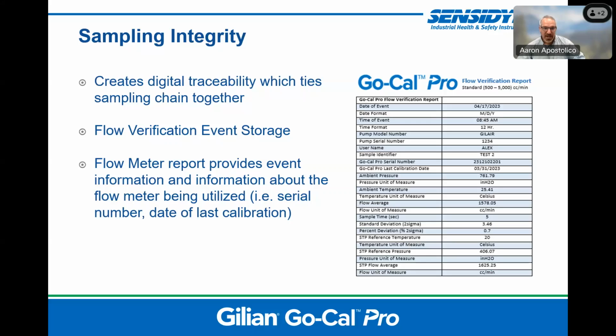Now, this flow verification event can be stored and data entry can be performed using that color touchscreen display. The flow meter report actually creates an event that can be downloaded and printed out. And this will give you information, again, about the flow meter, when it was last calibrated, and then tied together, as I mentioned before, your sampling pump, your user information, as well as your sample ID.